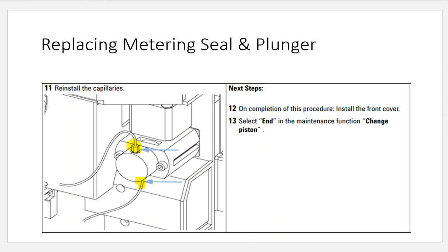Connect the two tubing lines back together, and now you get a hopefully analytical head that is going to be able to have the suction power that you need with very few leaks that you're going to see now, and your reproducibility is going to be much, much better than what it was before.